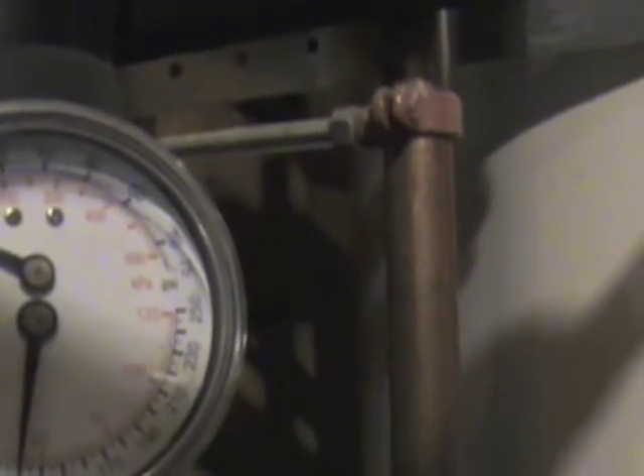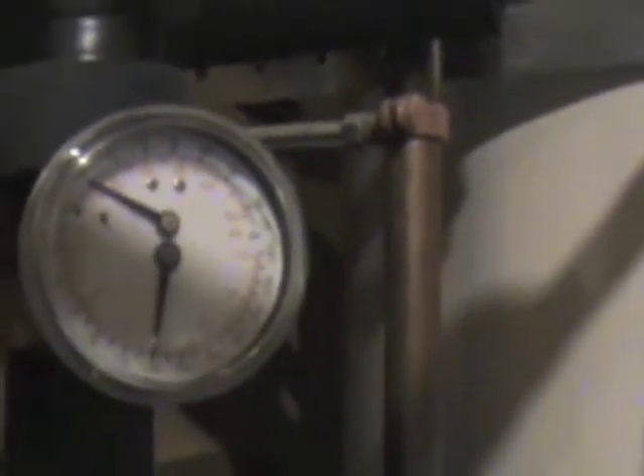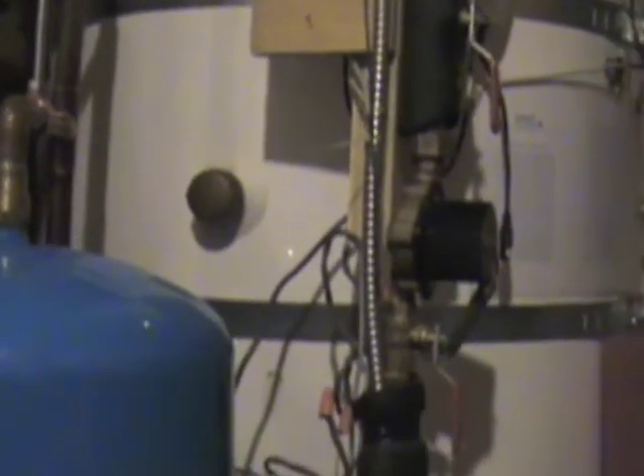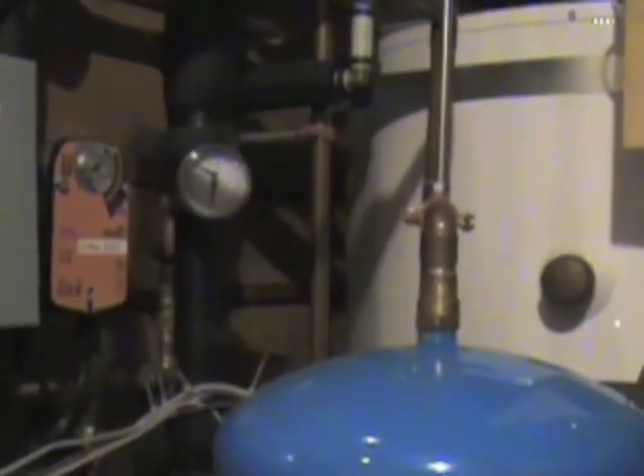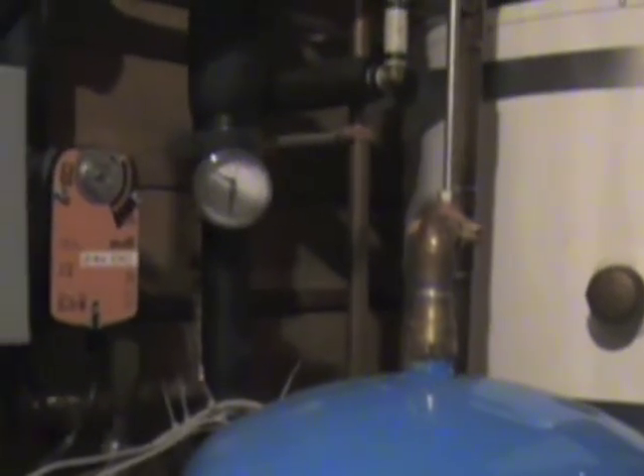Right now, if we look at this other little LCID pump, you can see two little red lights on — that means we're making solar hot water, lots of it. Over here we can see the temperature: about 130 degrees Fahrenheit or about 55 Celsius, so we're making pretty good hot water. This solar hot water is a combination system — it feeds both our domestic hot water and our space heating. And then it ties in with the wood gasification boiler, so it's all integrated here.